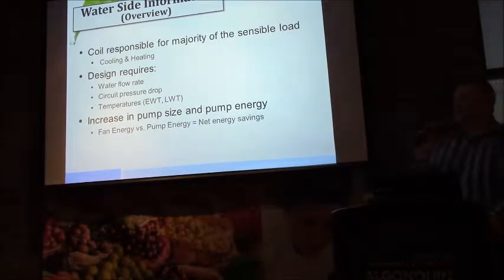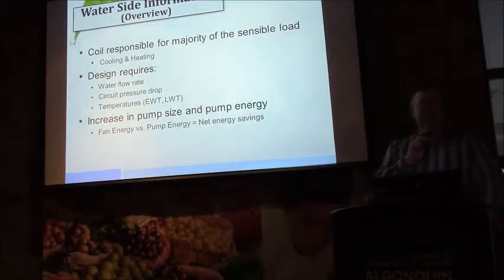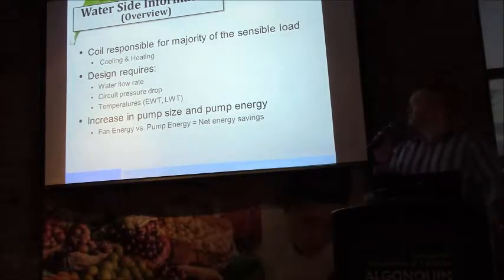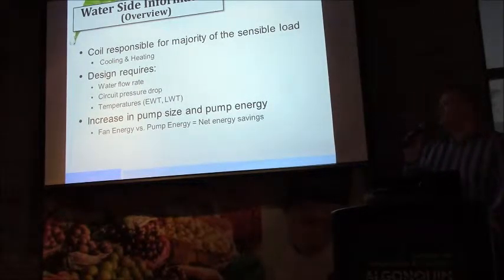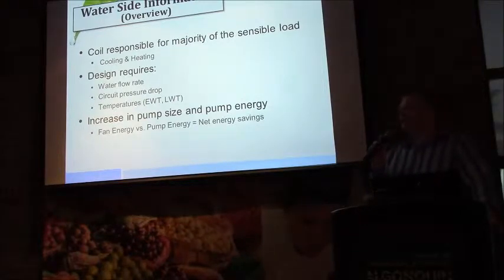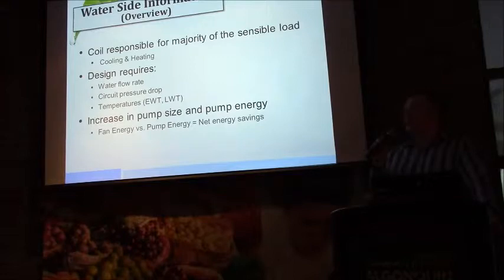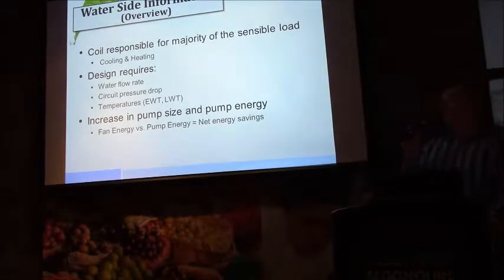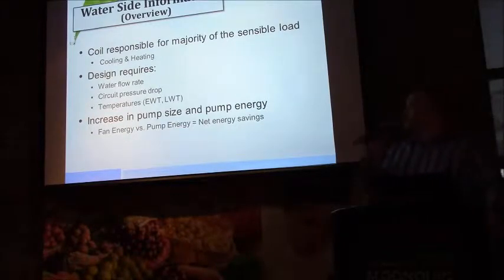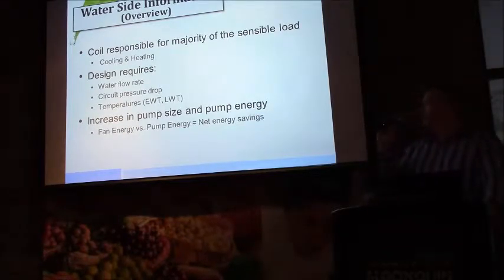And on the upside, the maximum water pressure drop that's allowable to the system, which generally is 10 feet, although as a design engineer, you may prefer to have less than that. And on an 8-foot coil with 2.5 GPM, we'll be in the 7 to 7.5 foot water column pressure drop for that coil. And there's options on coils in terms of being able to circuit them as either a single serpentine or headered. And then the entering water temperature.